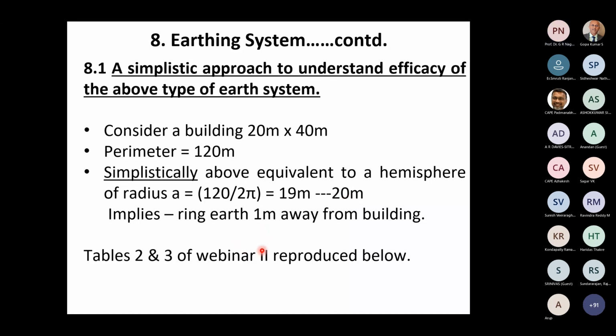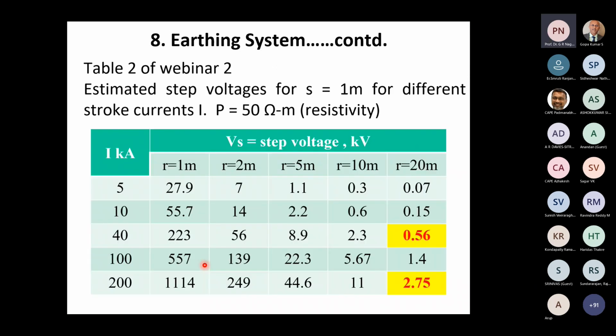We have reproduced here tables 2 and 3 of webinar 2, where we have estimated the step voltages for various currents, right from 5 kiloamperes to 200 kiloamperes, at various distances. Now, consider 5 kiloamperes at a distance of 1 meter. This is for a step spacing of 1 meter and a soil resistivity of 50 ohm-meters, which is considered a very good soil most of the time. If it is garden soil, it may be 1 to 10 ohm-meters, but for all other soils, 50 ohm-meters is an acceptable figure.